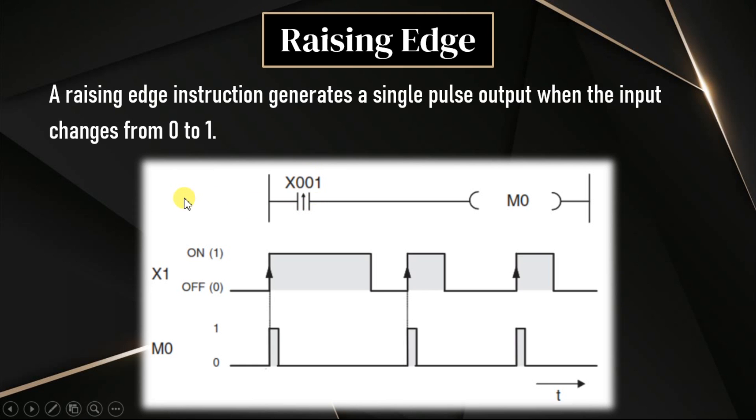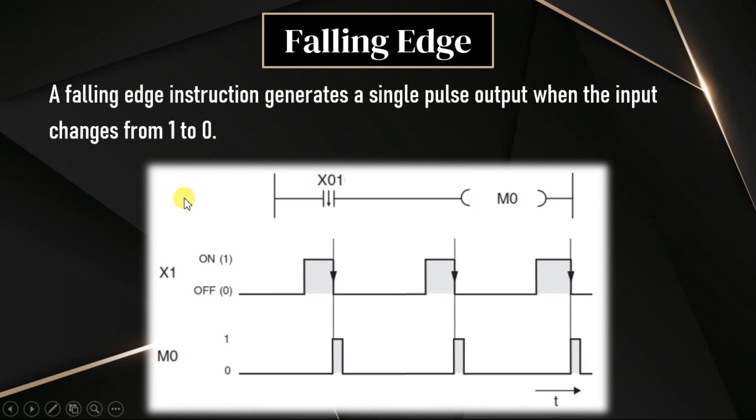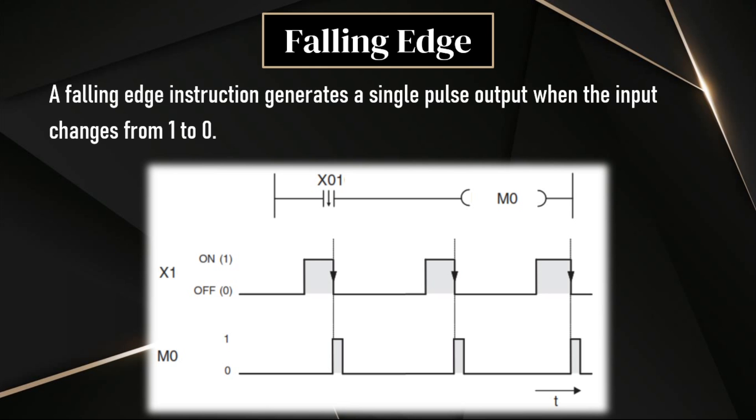Similarly, for falling edge, the instruction is represented with a down arrow. Falling edge is opposite to the rising edge. The output will be turned on for a single pulse when input is changed from 1 to 0, on to off. See here, when input is changed from 1 to 0, output is turned on for a single pulse. We will see this in our software.